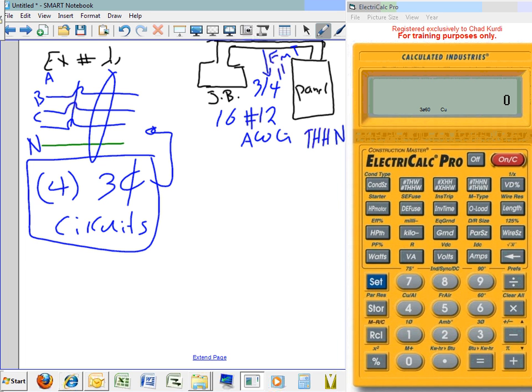Okay, everybody can see the scenario is I took a 3/4 of an inch conduit from a panel all the way to a J box right in the ceiling, and I filled that conduit with 16 conductors number 12. Can I do that fill-wise? Yes. If you guys go to the conduit fill EMT, you can find that's the max that you can put there, 16 number 12, right? And Chris is nodding his head indicating yes.